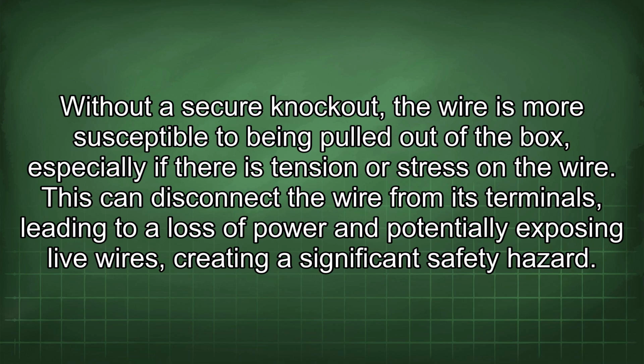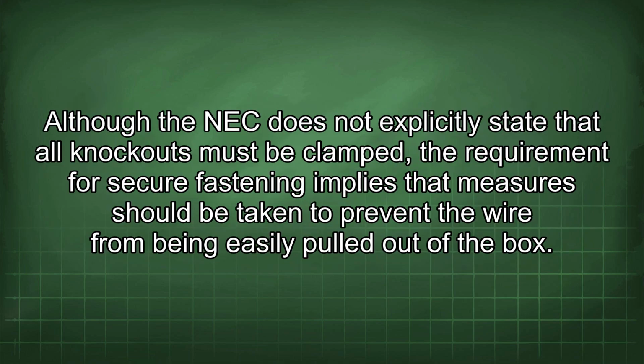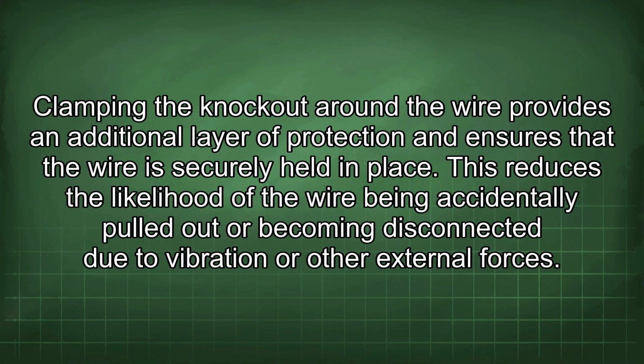Although the NEC does not explicitly state that all knockouts must be clamped, the requirement for secure fastening implies that measures should be taken to prevent the wire from being easily pulled out of the box. Clamping the knockout around the wire provides an additional layer of protection and ensures that the wire is securely held in place.